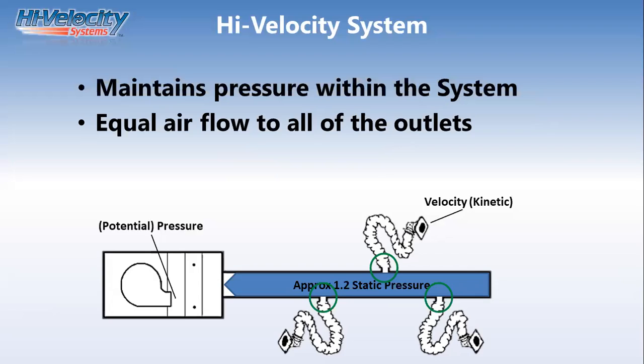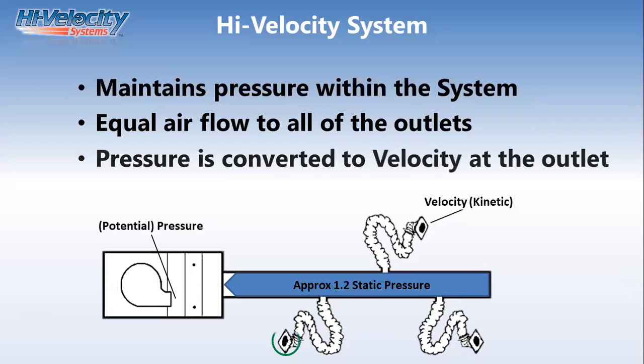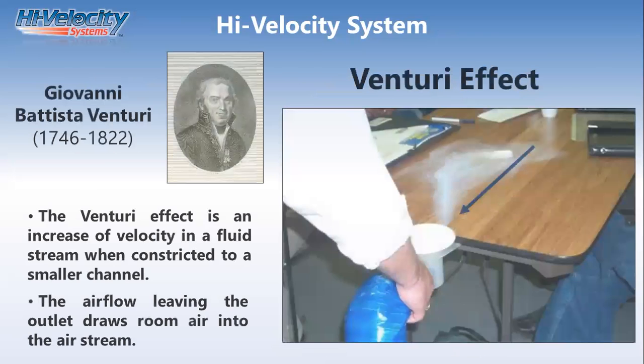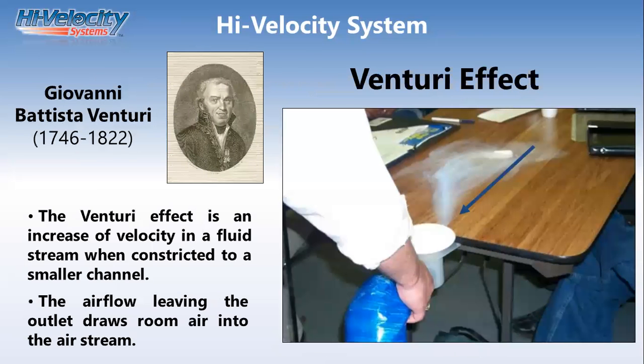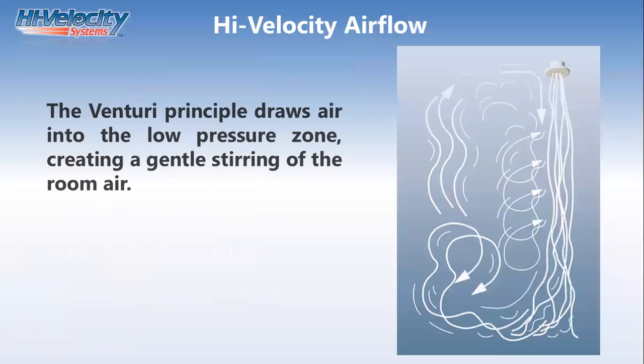The balancing is done during the duct design, which is a free of charge service offered at our factory. Now, the real magic of what happens with a high velocity system is at the termination point, when we convert that pressurized airflow to velocity entering the space, creating the Venturi effect. As that airflow exits out of a high velocity outlet, it is going to draw in the regularly stagnant room air all around it and force a total mixing of the room air.